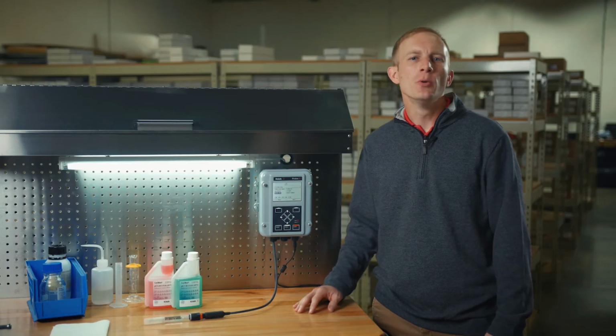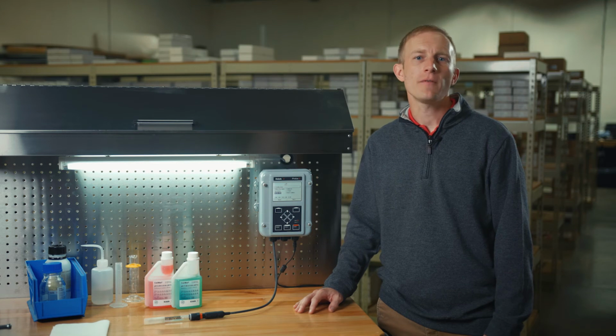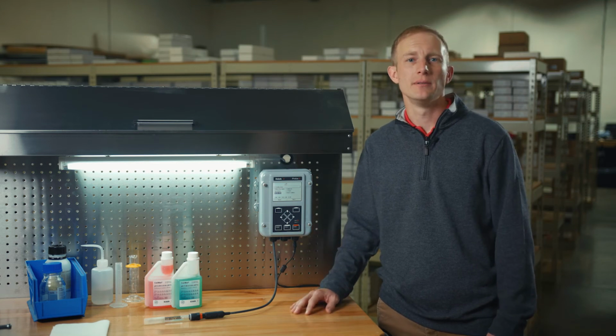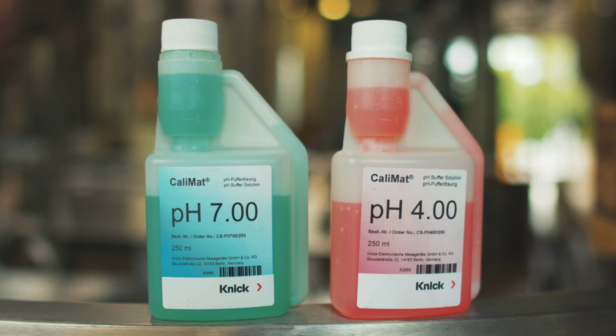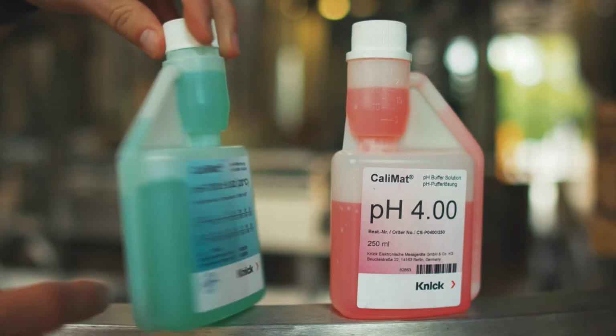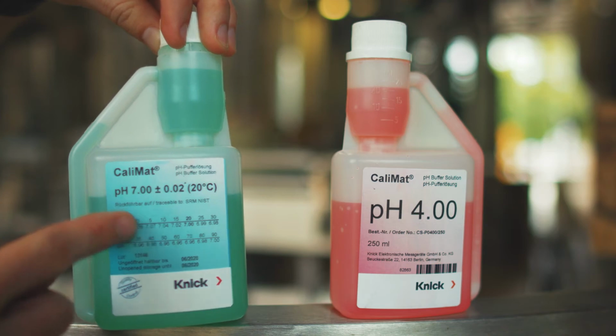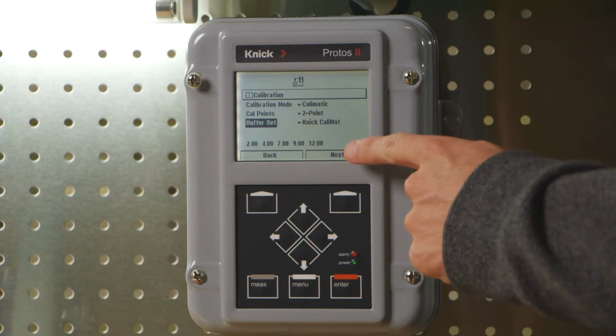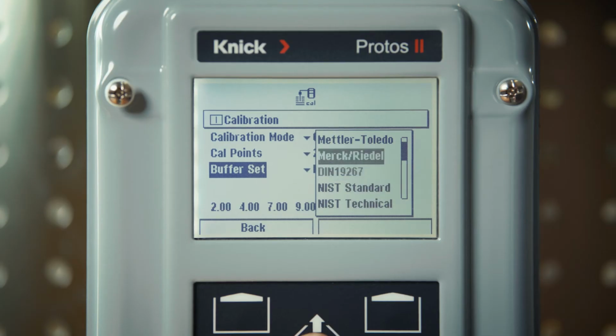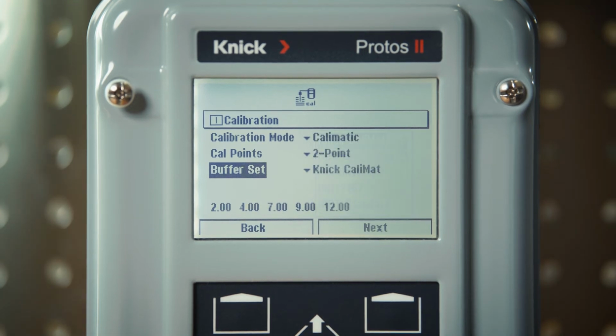The Protos has numerous buffer tables stored within its software for selection by the operator. It's important to note that NIST Technical is most commonly used. Verify your buffer values by cross-checking the labels against the values on the bottom of the screen. We will select the Knick CaliMat buffers and press Enter to continue.